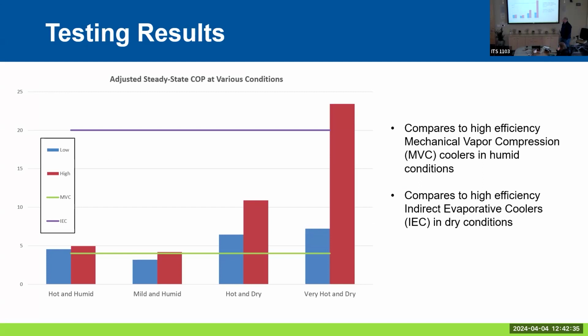So here is a quick comparison of how this looks compared to some other items. If you take the COP of a high efficiency air conditioning unit, you get around 4. And if you take the COP of a very good indirect evaporative cooler, you get around 20. So, in most of our instances, we beat or came close to a high efficiency air conditioning unit, and in some hot and dry situations, we did very well compared to indirect evaporative coolers. So this is a good system that can help us in all climates: hot, dry, wet, and mild.